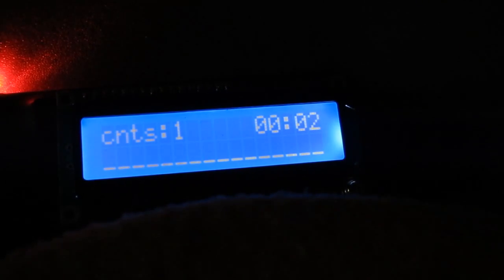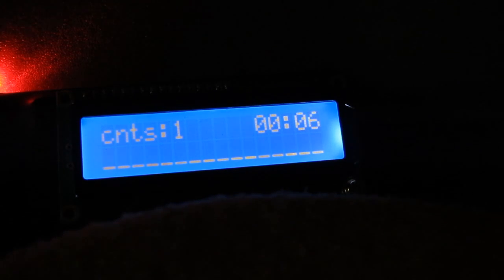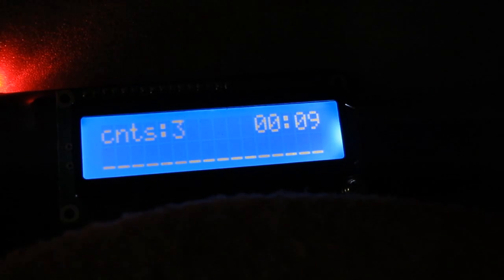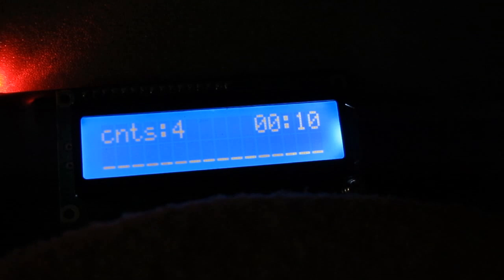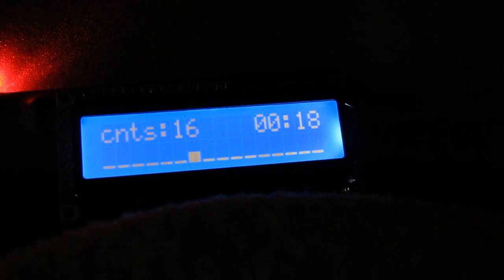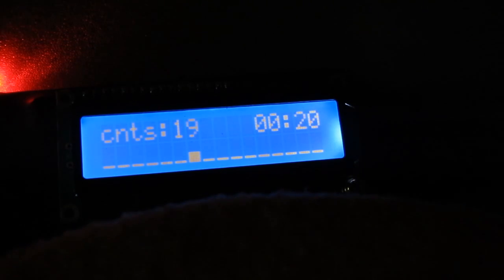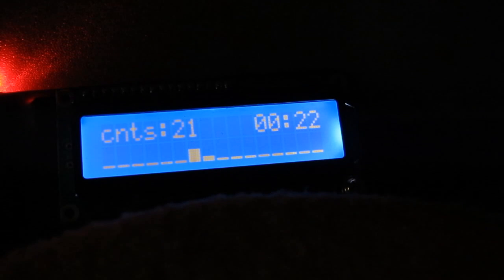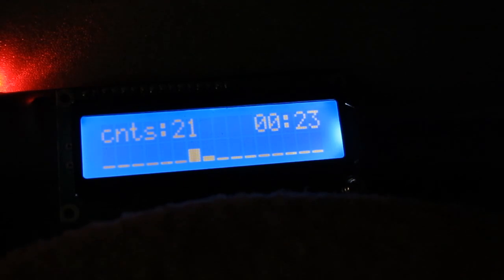Performing test with 80 kV, 25 mA, 500 ms. Pretty much didn't see anything there, but you could see that the camera saw the x-rays, so there was radiation there.